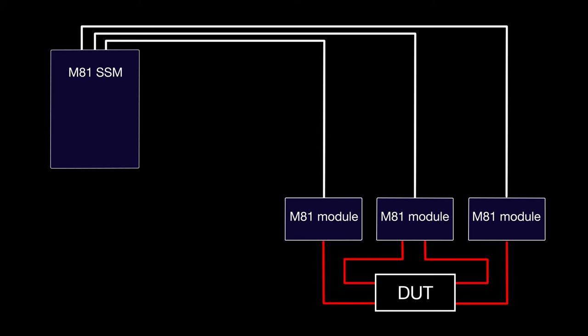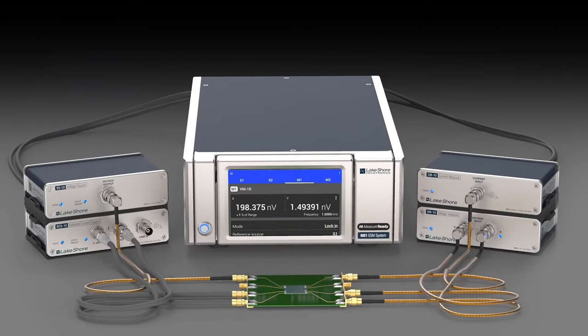This reduces signal cabling length and associated leakage, noise and settling times, particularly critical at the ultra-low signal levels inherent in a cryogenic temperature characterization application.